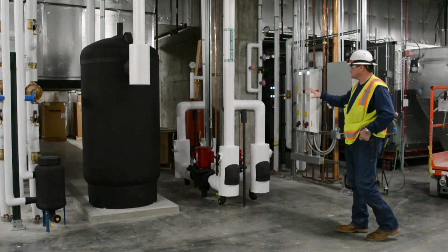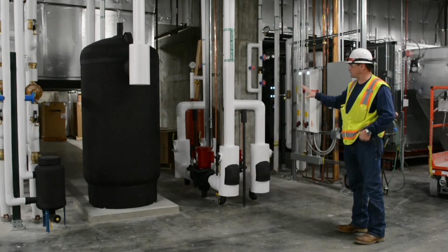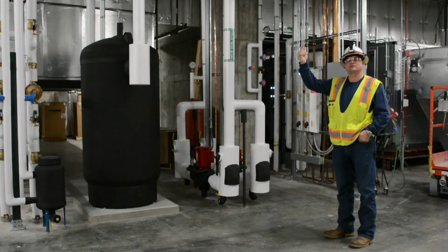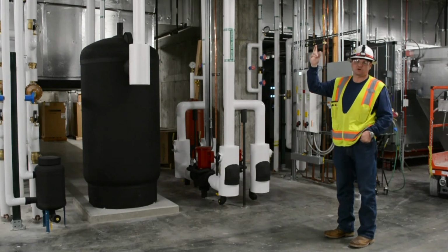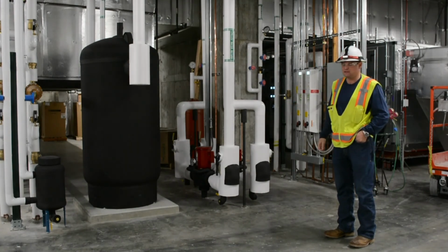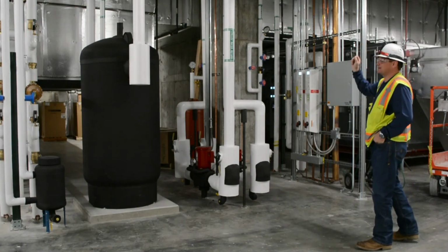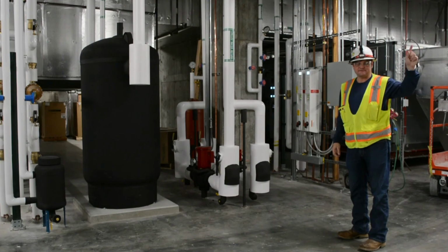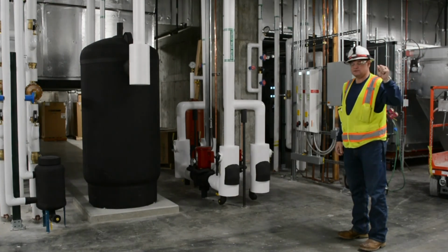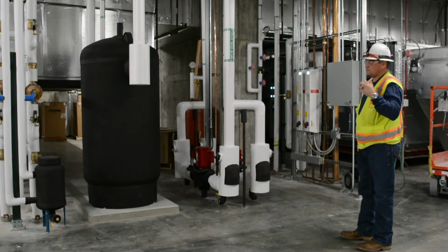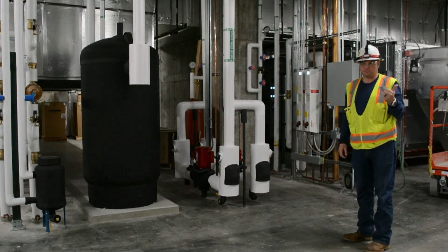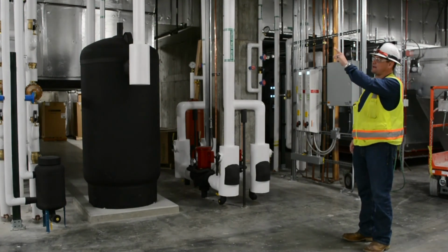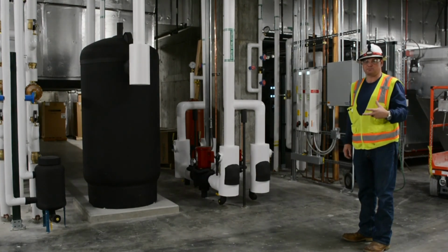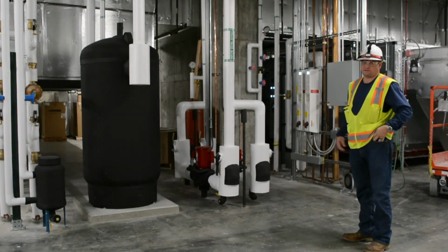The primary use for this machine is for the backup chilled water to the data center. In the event the central plant chilled water fails, there's automatic valves that will switch over and start this chilled water system up. The remote evaporator is located here, and the condensing unit is actually on the roof of the OPC building, near the OPC building. The only thing you'll have to do there is check the coils for debris and clean those annually. Again, this chiller will run very, very small amounts of time, if any amount of time. And the automatic switchover is all based off of temperature. So if for some reason the central plant chilled water temperature gets above 50 degrees, this will automatically start and take over.